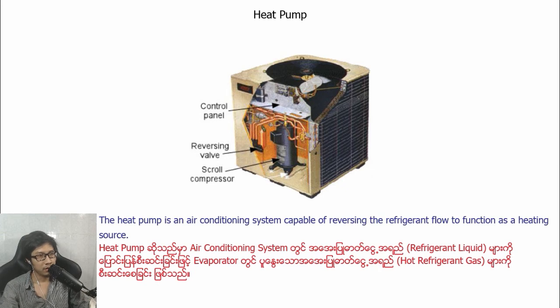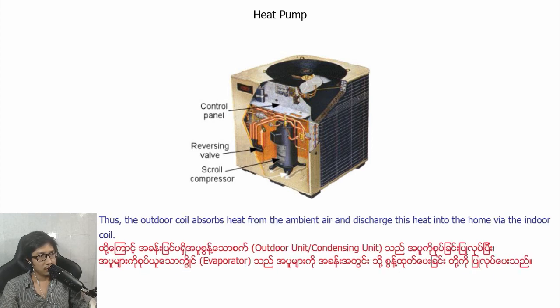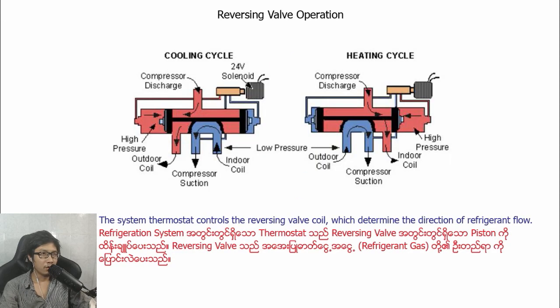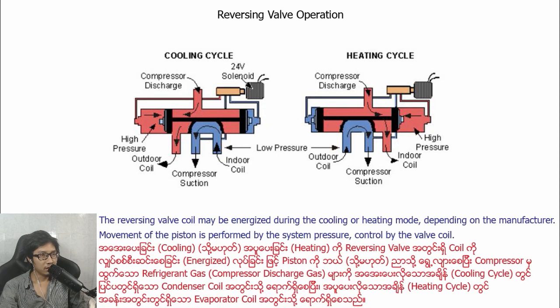Heat pump. The heat pump is an air conditioning system capable of reversing the refrigerant flow to function as a heating source. Thus, the outdoor coil absorbs heat from the ambient air and discharges this heat into the home via the indoor coil. Reversing valve operation. The system thermostat controls the reversing valve coil, which determines the direction of refrigerant flow. The reversing valve coil may be energized during the cooling or heating mode, depending on the manufacturer.